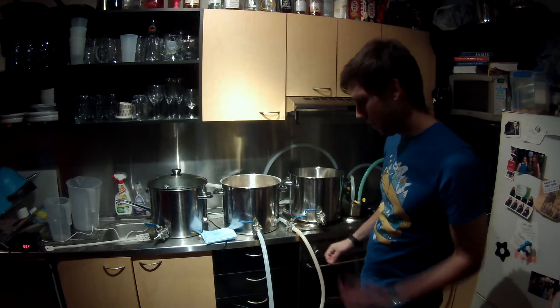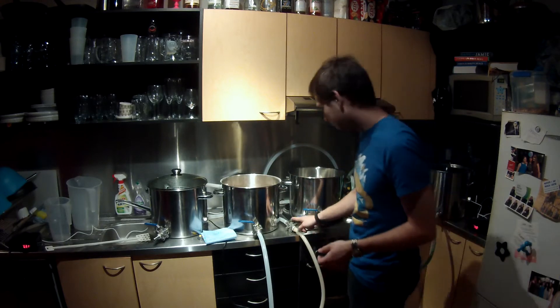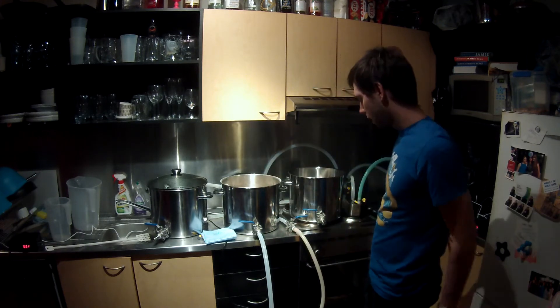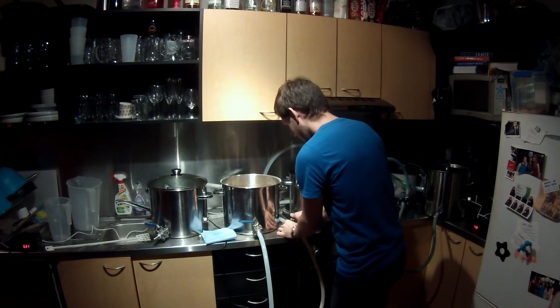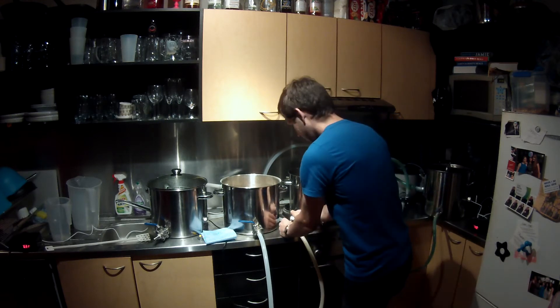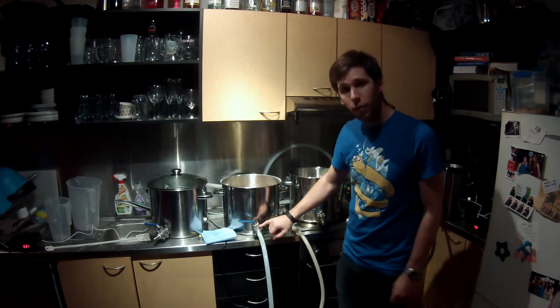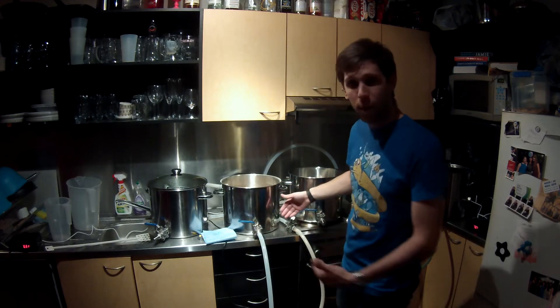What I'm using to restrict the flow is just a three-piece ball valve with two barbs on either end. I'm going to let it trickle through to start with - just enough so it primes itself but doesn't go too far. About half way open. Don't choke it from behind the pump - you'll ruin your pump. Choke it from after the pump.